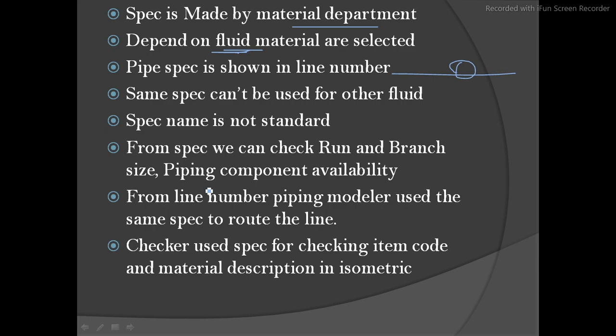For branch size — if you have a main size of 10 inches and a branch connecting to 4 inches, you don't know whether to take a reducing tee or a stub-in. So you go to the spec and check what exactly is specified for 10-by-4. From there you can determine whether to do a weldolet or some other branch connection. Whatever branch connection is required, you can find it in the specification.